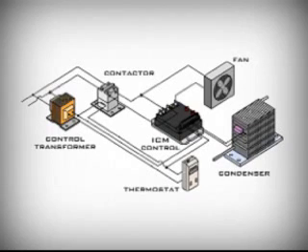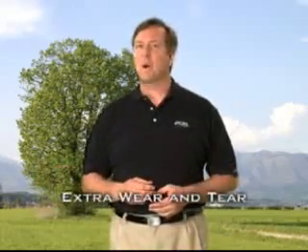As the fan slows down, it pushes less air through the condenser, so it sheds less heat energy. It's like being able to change the volume of the condenser coil. Instead of the all-or-nothing approach that other head pressure controls take, ICM's low ambient fan speed controls make sure the condenser fan always runs at the correct speed for maximum efficiency. Head pressure is maintained without inconsistent cooling, clanking pipes, or the extra wear and tear that can shorten the lifespan of your equipment.